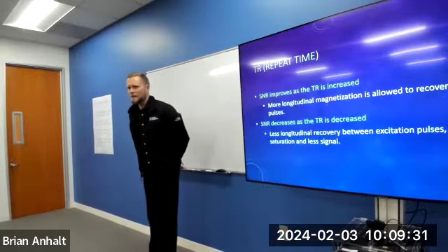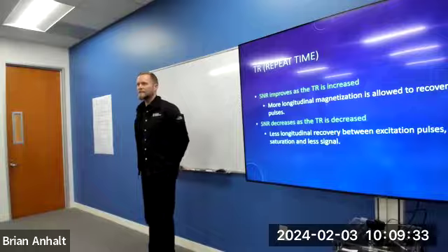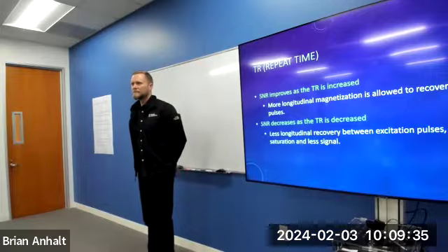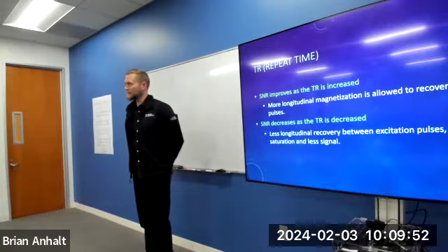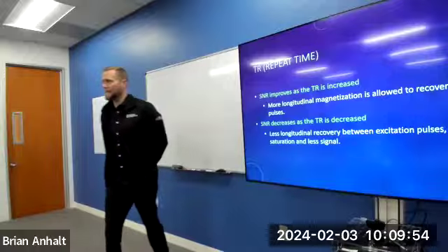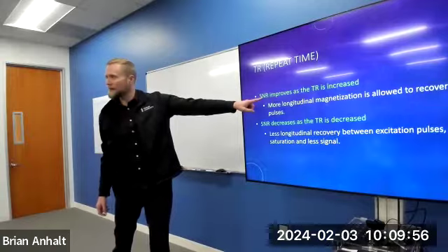But we know that if we want T1 weighting, we need a short TR, right? So we're already affecting our SNR to get better T1 contrast, right? So what's the trade-off right there? Lowering my TR gives me better T1 weighting, but I'm sacrificing what? SNR, right?